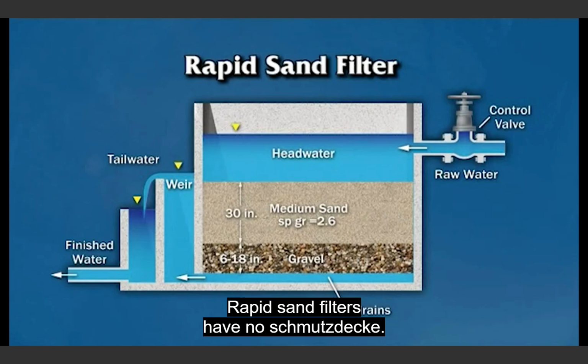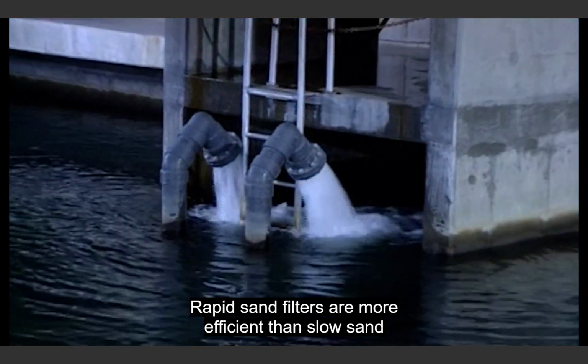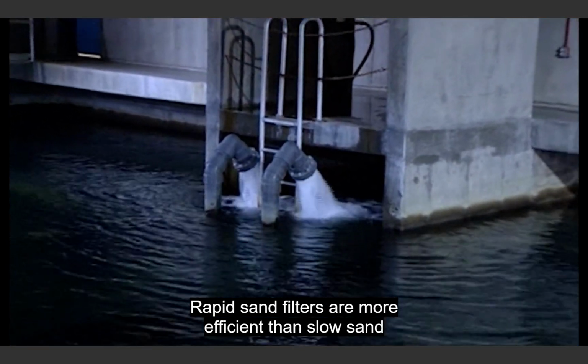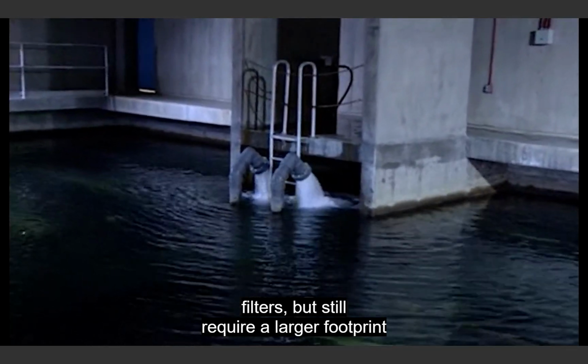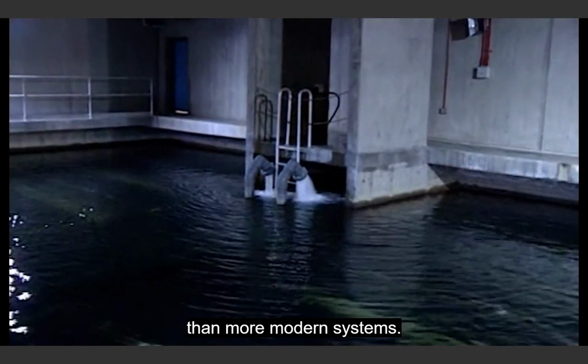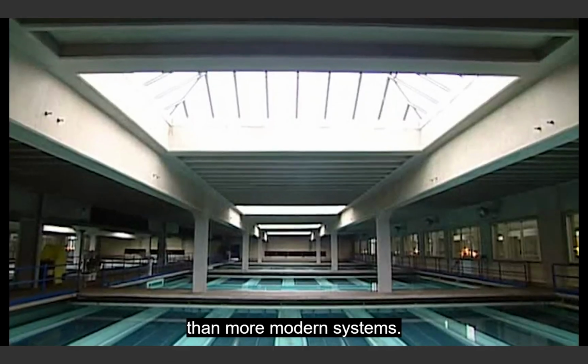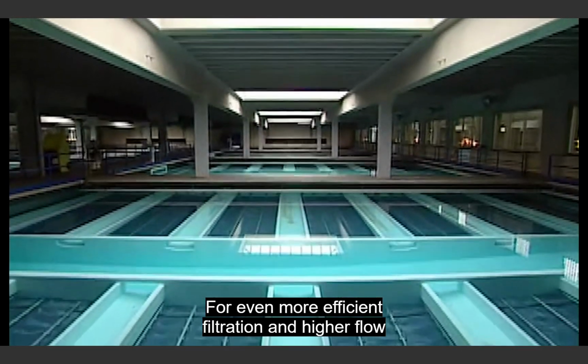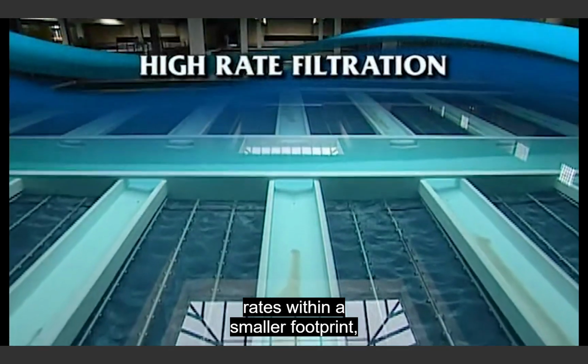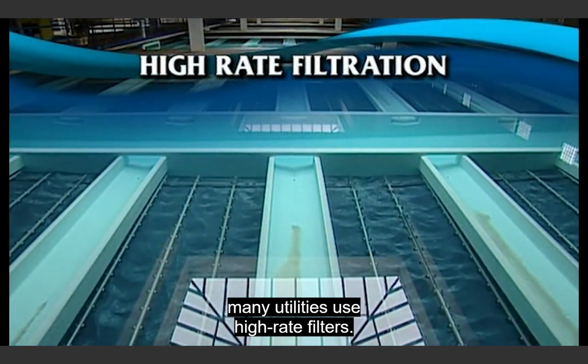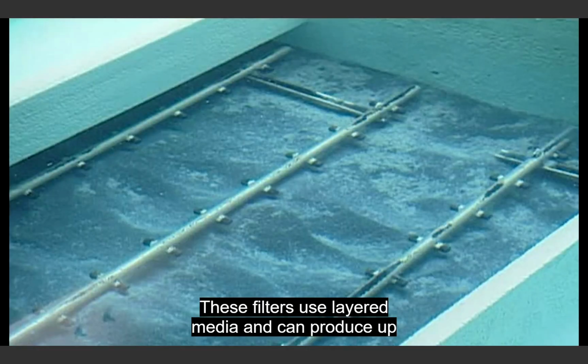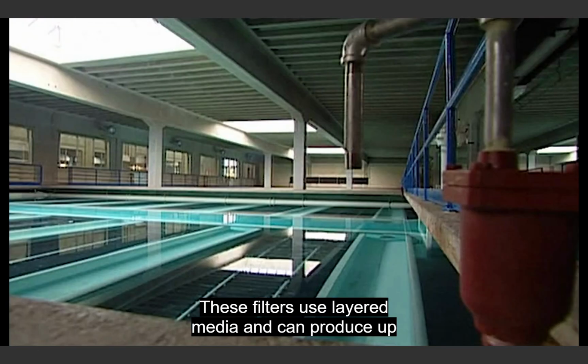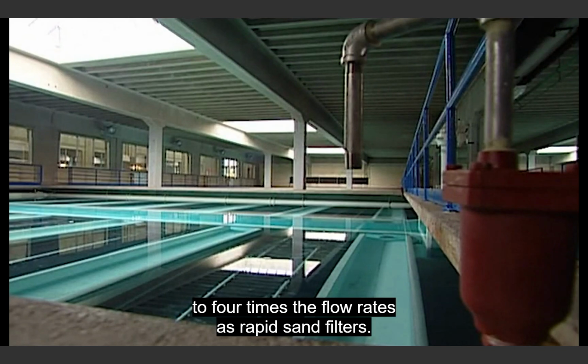Rapid sand filters have no schmutzdecke. Rapid sand filters are more efficient than slow sand filters, but still require a larger footprint than more modern systems. For even more efficient filtration and higher flow rates within a smaller footprint, many utilities use high-rate filters. These filters use layered media and can produce up to 4 times the flow rates as rapid sand filters.